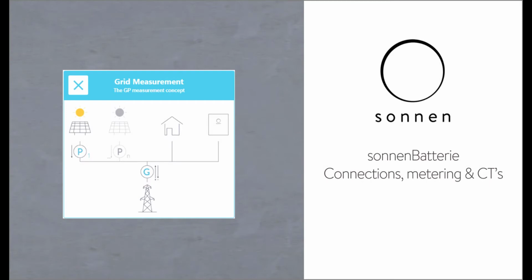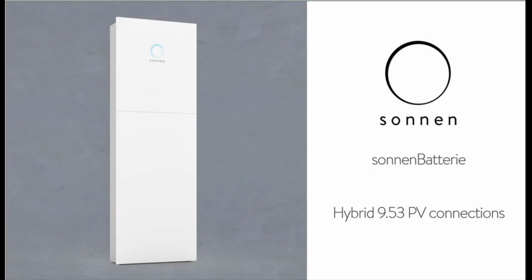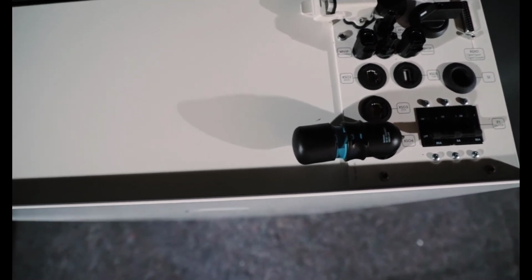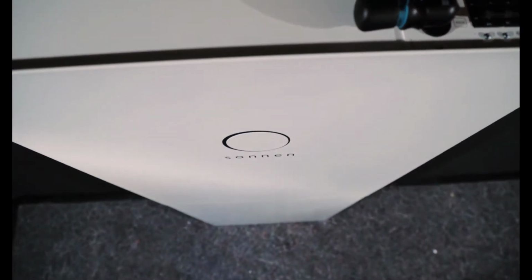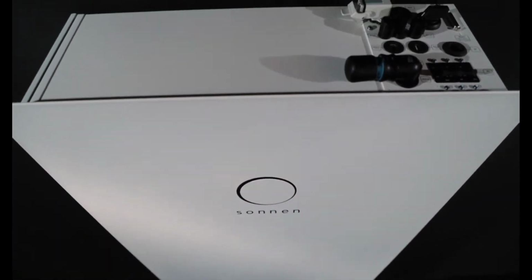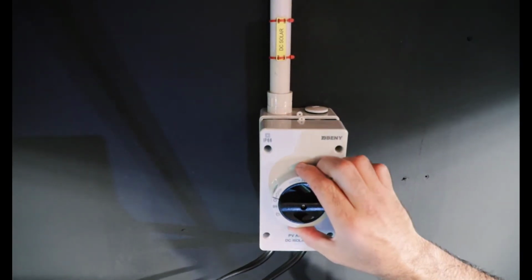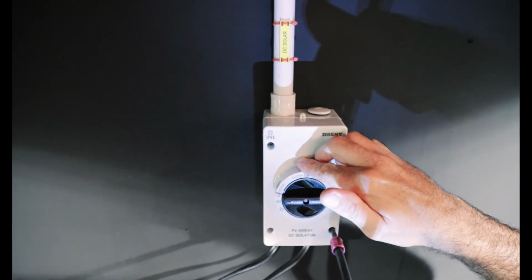So we're going to have a look now at the main connections of the sonnenBatterie system as well as the metering and CT setup. First thing, the hybrid 9.53 has the ability to take PV directly into it. So we're just going to very quickly have a look at the connections. I'm not going to show you how to do the entire PV installation, so we're just going to take it directly from the associated DC isolator.